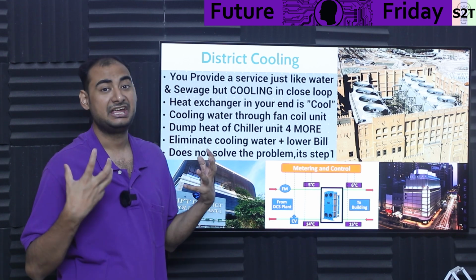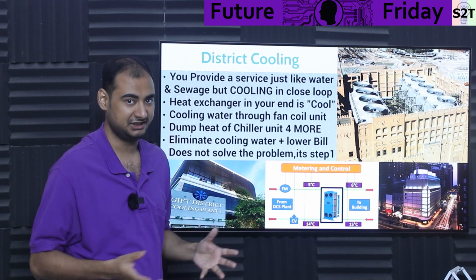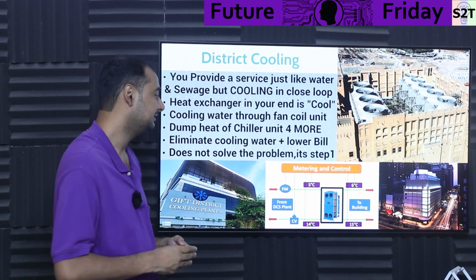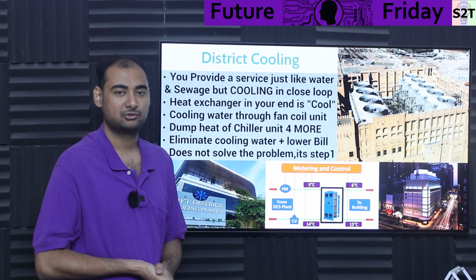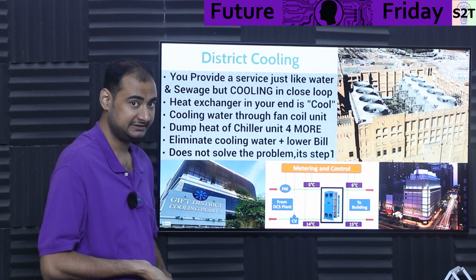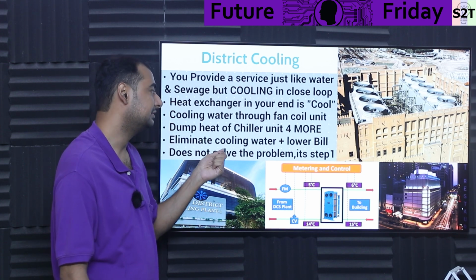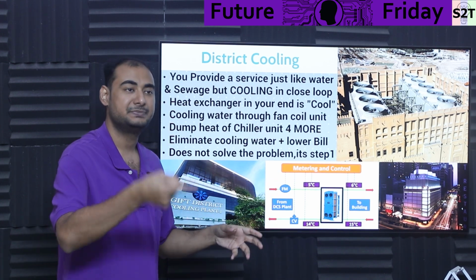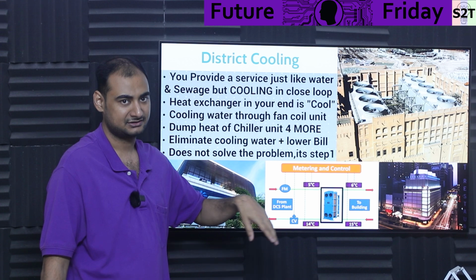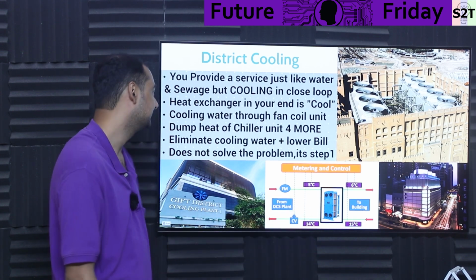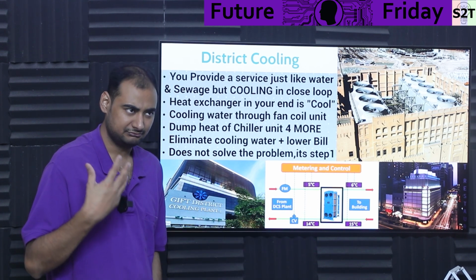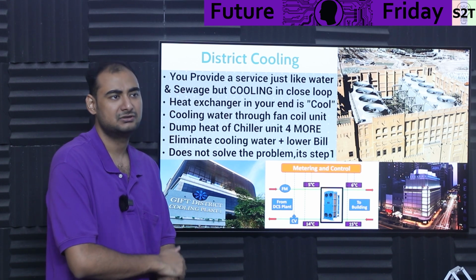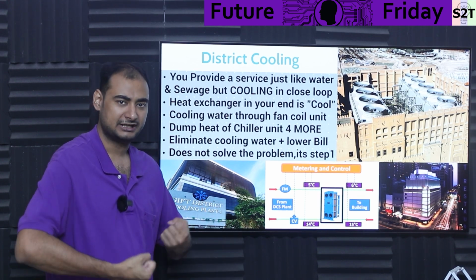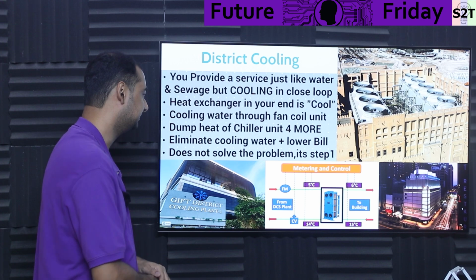Now what if you have a heavy load, like computers or office buildings consuming serious power? In that scenario, water may not be adequate to create the temperature delta you're seeking. So people use a chiller and dump its condenser loop into this system. The same thing happens, and most of the time fan coil units are good enough, but sometimes you need that extra oomph, so that can be done.